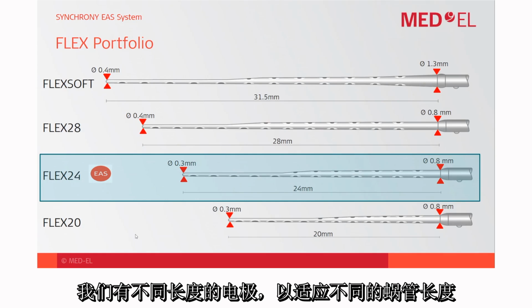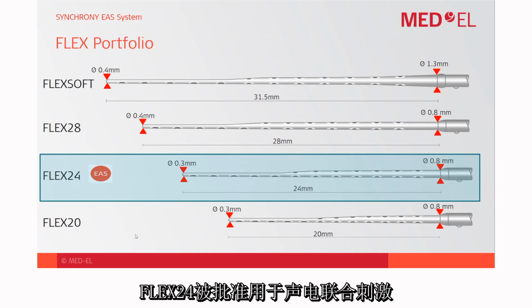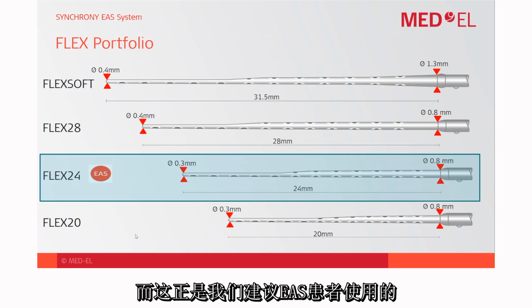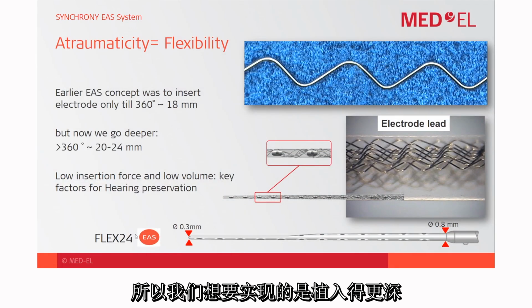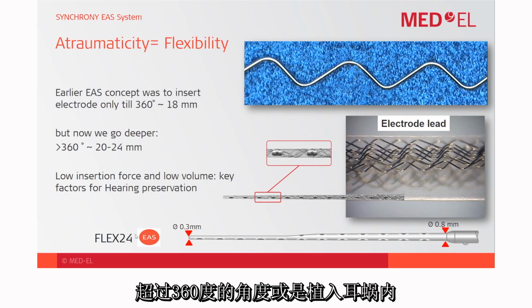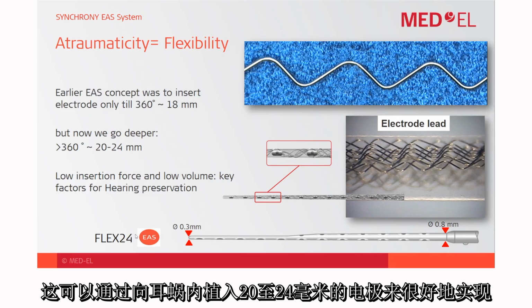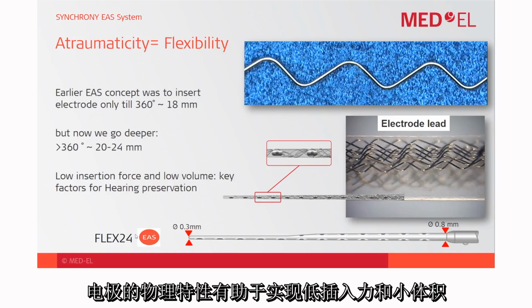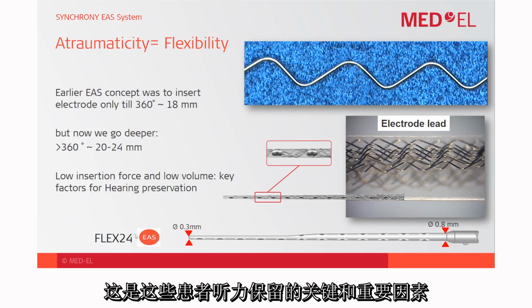As you see here, we have different lengths of electrode to suit different lengths of the cochlear duct. The Flex 24 is approved for EAS indication, and this is what we would recommend to use in EAS patients. What we are trying to achieve is to go deeper, further than 360 degrees of angular insertion inside the cochlea, and that can be achieved very nicely with 20 to 24 millimeters of electrode insertion. There is growing evidence in the literature that they are no longer talking about the absolute length of the electrode itself, but more and more about the angular insertion depth. That is why it is very important to go more than 360 degrees inside the cochlea when doing the EAS procedure. The physical properties of the electrode help achieve low insertion force and low volume, which are key and important factors for hearing preservation in these patients.